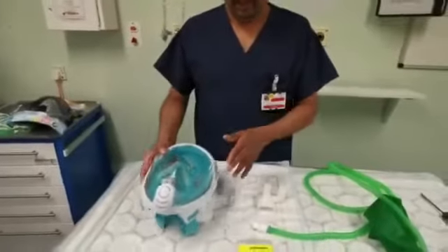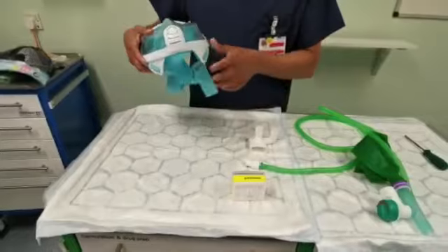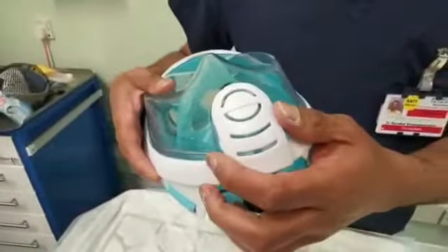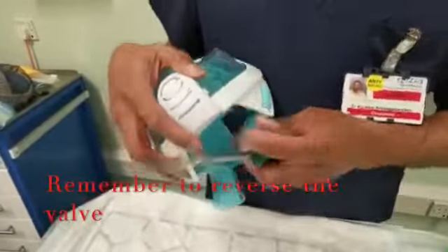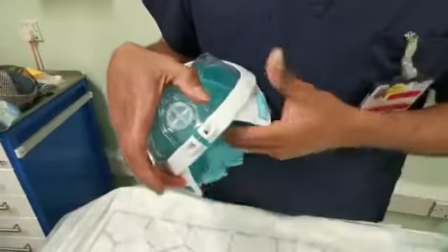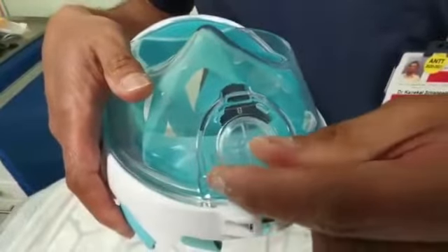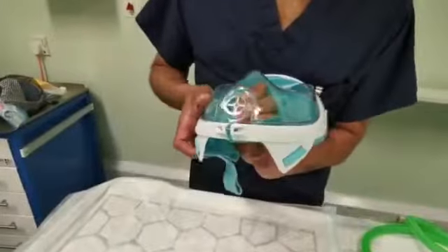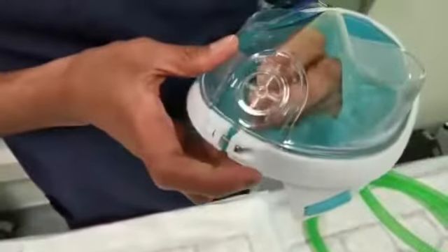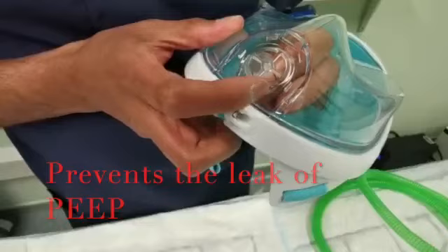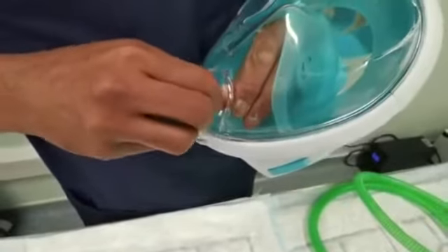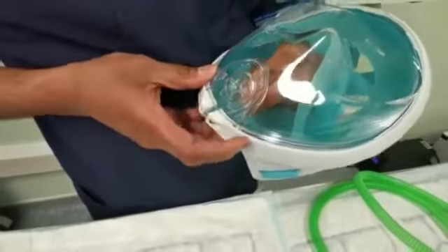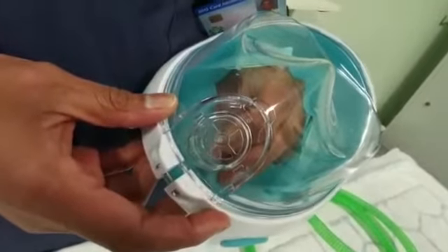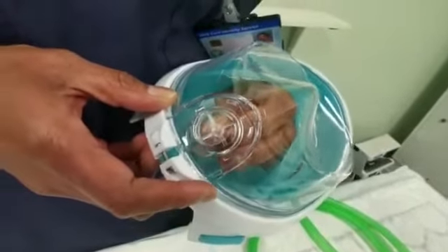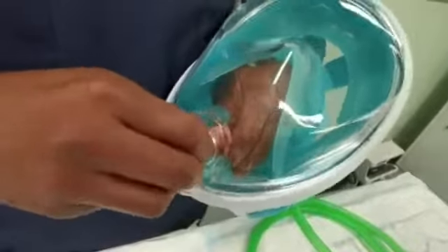So we just need the mask, and in this mask we have to convert a single one-way valve which sits at the bottom of the mask. We basically need to make it non-functional. The way we do it is we take this plastic attachment out, and you can see there's this silicon valve which is actually a one-way valve, connected with a nipple. So you essentially take this valve out and put it back inside from the other side so that it makes the valve non-functional. Every time there's positive pressure in the mask, the valve shuts and there's no leakage, the positive pressure is maintained and the patient breathes. It's a bit fiddly, but you don't have to do it again and again. Once you do it, it is there for you to use the mask effectively.